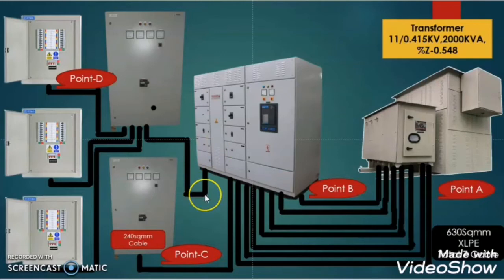As I told you in my discussion, we have to calculate the prospective short circuit fault current at each relevant position in the electrical installation. So in this video we will calculate the short circuit prospective fault current at point A, point B, point C and point D.